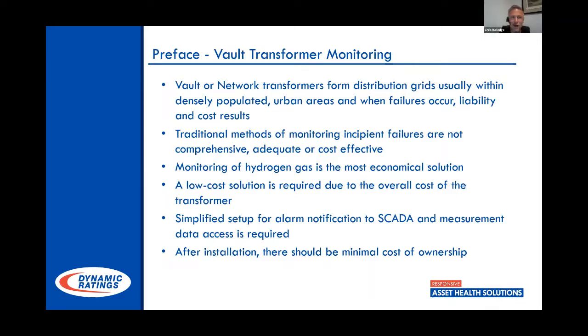But I've talked to a lot of customers since I've been on this side of the industry, and I'm finding that a lot of them are not looking at the pressure of the transformers or even worrying if there's nitrogen on the transformer. And so with this, these are subject to be submersible. So you do risk moisture ingress in these transformers, and that's a big piece of the failure.